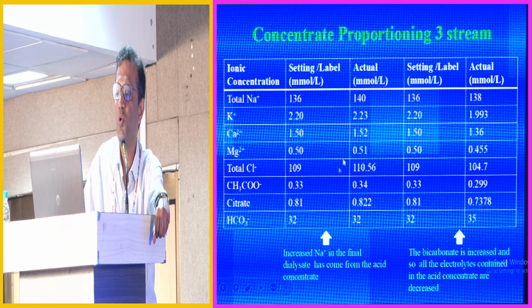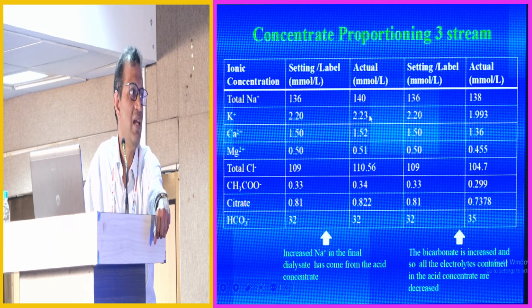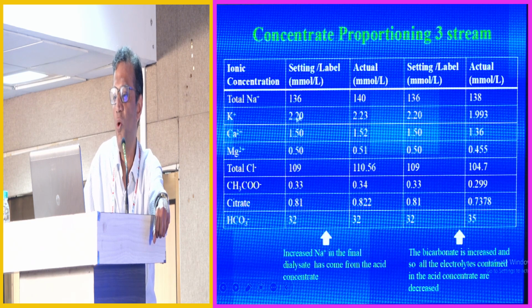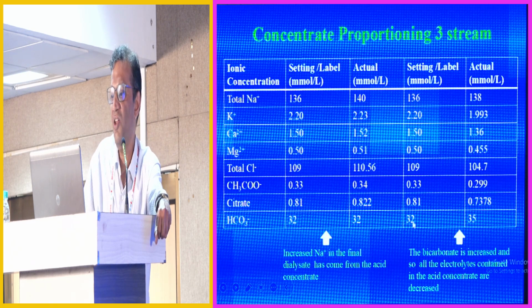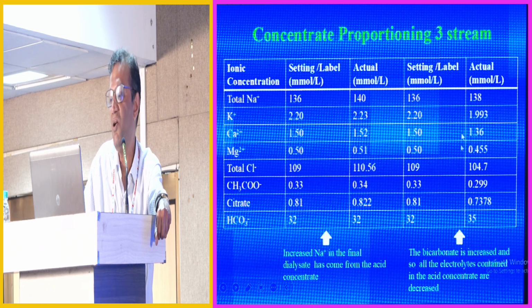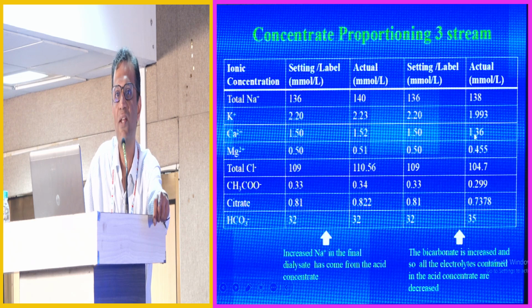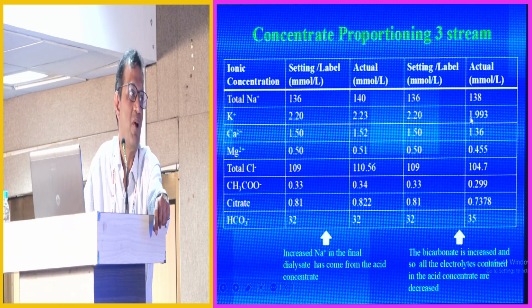If we increase the sodium from 136 to 140, leaving the bicarbonate at 32, then all the other electrolytes coming from the acid concentrate will increase slightly. So potassium goes from 2.2 to 2.23, calcium to 1.52, not really significant, but it can change. If on the other hand we choose to increase both the sodium and the bicarbonate, the additional sodium is taken from the B concentrate, and so all the electrolytes coming from the acid concentrate will actually slightly decrease. So potassium has gone from 2.2 to 1.99 here.